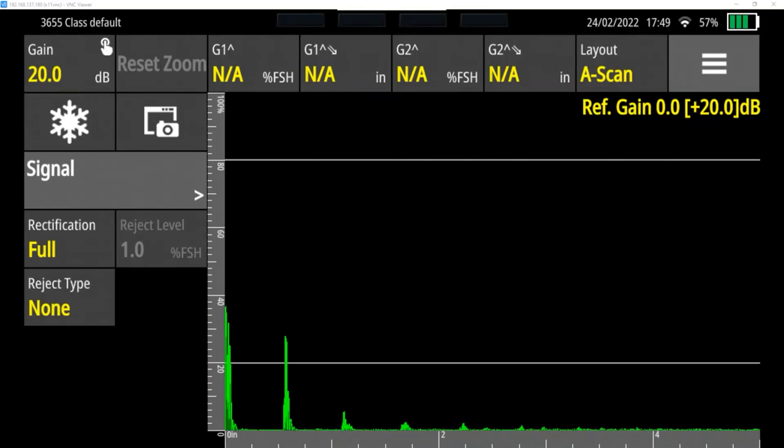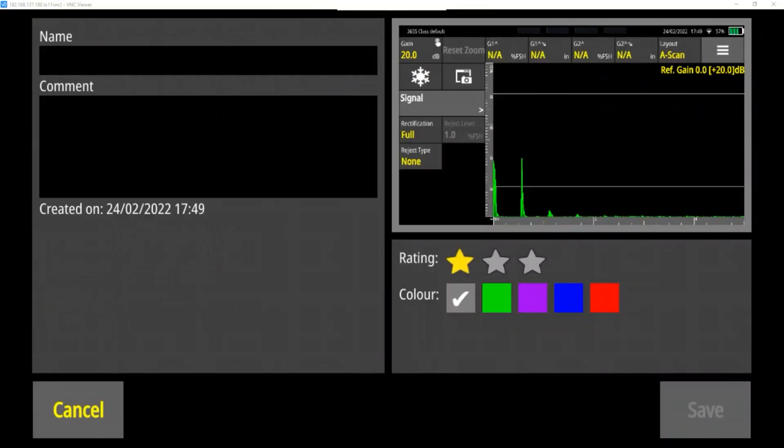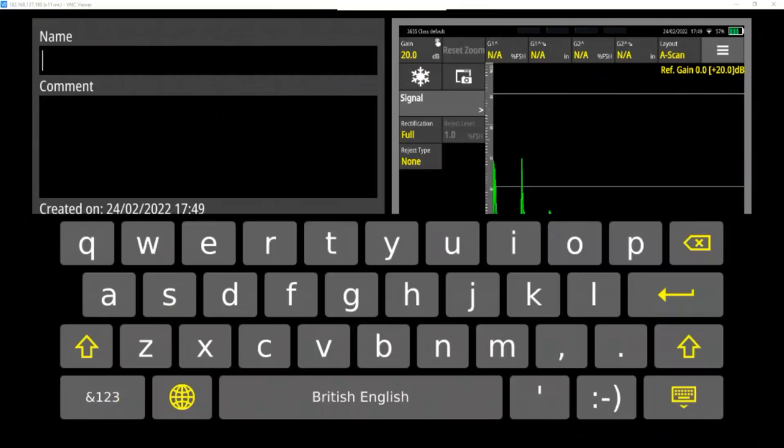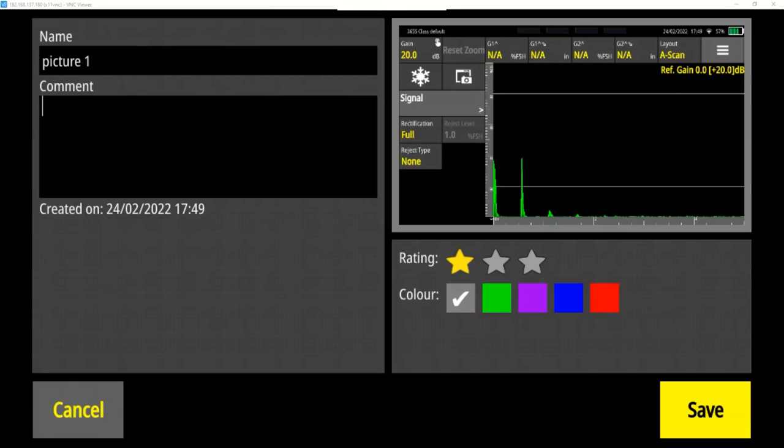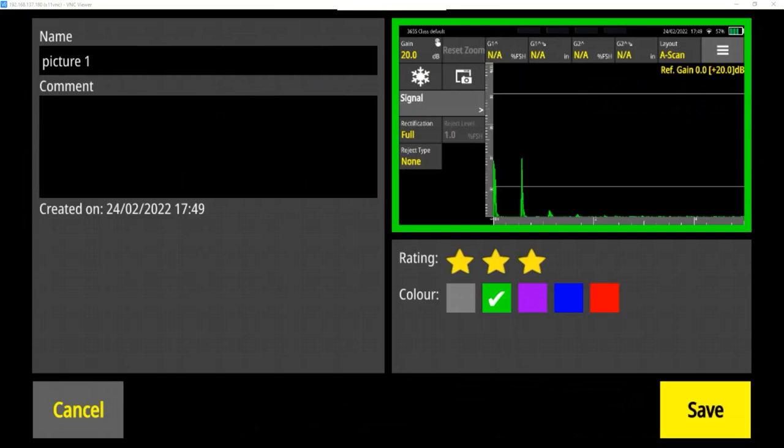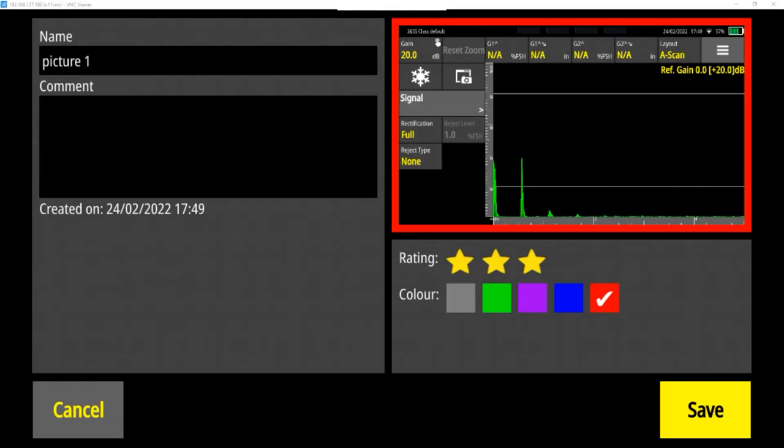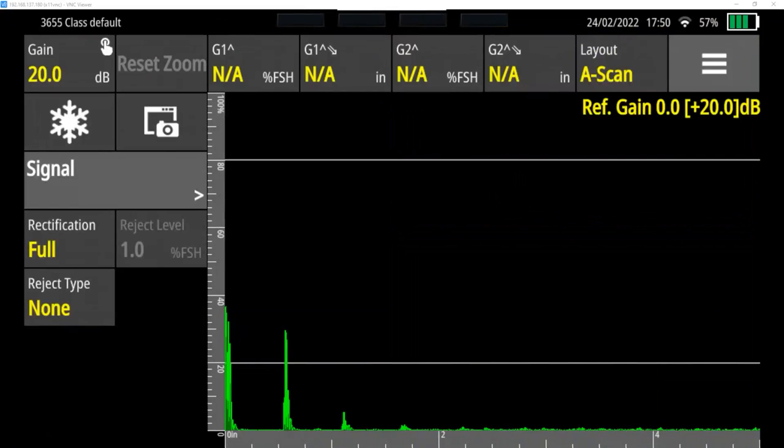Next to that snowflake is a picture. And I can take a picture either while it's in live mode or while frozen. So if I hit the picture button, we'll get a picture here and I can name it. If I want to comment on it, I can add that as well. When I'm done with the keyboard, I press the little keyboard icon. I can decide how good my picture is and can give it a rating. One to three stars. Also, color coding. In some industries, maybe if a part they inspect is okay, they give it a green rating. However, if you find a part that's a known flaw, you give it the red rating. Or you can do something in between, maybe if it needs follow-up. And then once I have decided what I'm going to do with it, I can hit save in the lower right. And I've saved the picture.